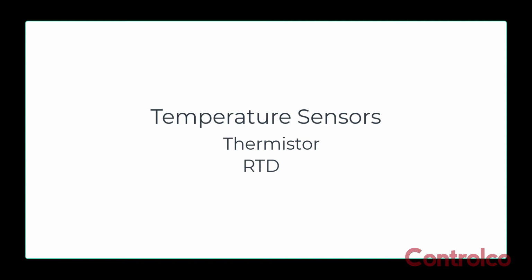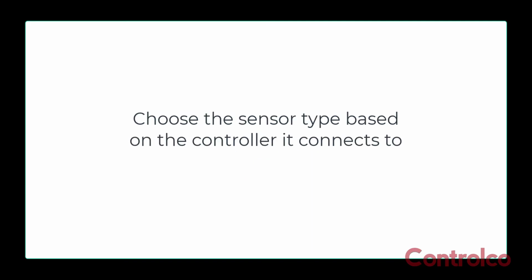RTD stands for resistance temperature detector, and they're specified based on ohms. So you'll have 100 ohm, you'll have 1,000 ohm, 5,000 ohm, and then the base metal that they're using. So that'll be platinum, nickel, there's a couple of other ones too. The one that you choose is going to be dependent on the controller that you're using. So some controllers want to see 1K ohm nickel RTDs, or they want to see 10,000 ohm thermistors.